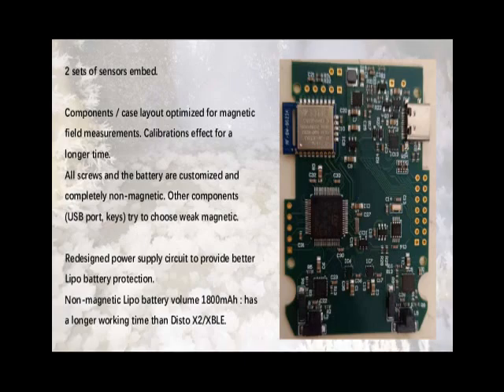This is the new main board of the new device. Two sets of sensors are adopted on the backplate. The results from these two sensor sets can be compared to distinguish whether there's calibration loss or magnetic field interference.